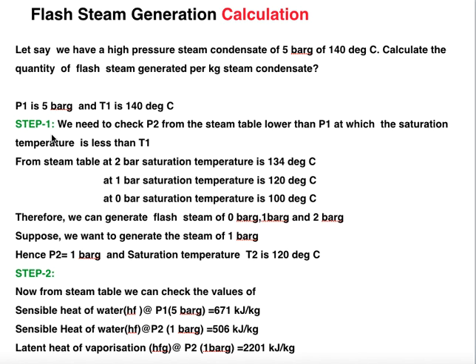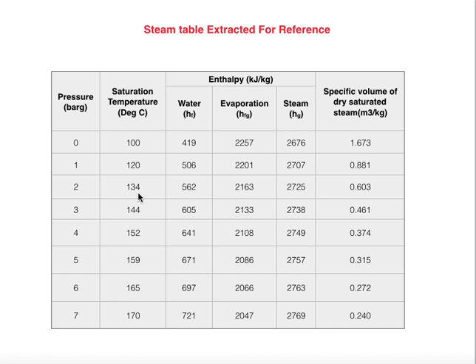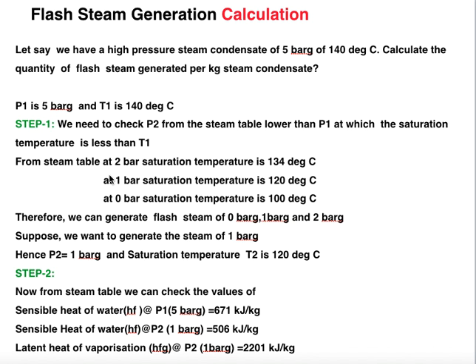From the steam table, at 2 bar gauge the saturation temperature is 134°C, at 1 bar gauge it is 120°C, and at 0 bar gauge it is 100°C — all lower than 140°C. So we can generate flash steam at 0, 1, or 2 bar gauge. Suppose we want to generate steam at 1 bar gauge; therefore P2 is selected as 1 bar gauge, and the saturation temperature T2 is 120°C.